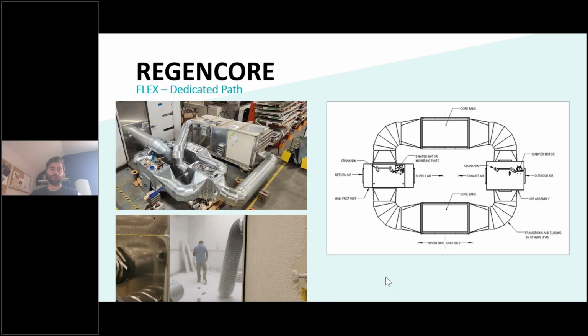So going back to carryover leakage and the mention of an indoor unit, counting the duct after those cores all the way to an outside wall is how long your carryover leakage is going to be. When that starts to become an issue, this dedicated path product, which is a 4th box, becomes attractive. Essentially, it closes the loop within your carryover leakage amount and provides dedicated outdoor air intake and a dedicated exhaust path from your unit. And inside there is just another set of dampers to allow that to happen.